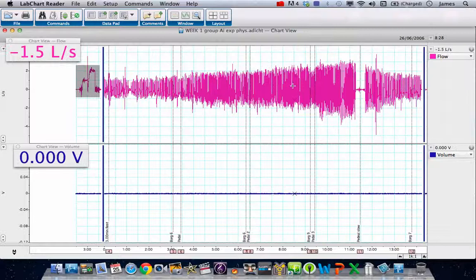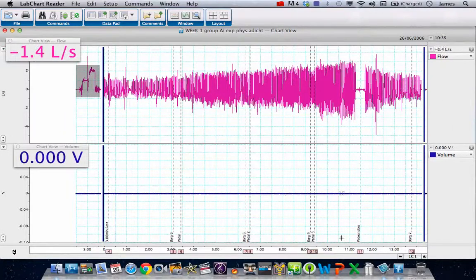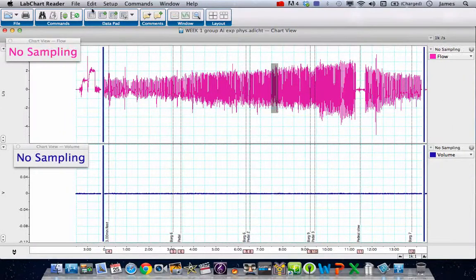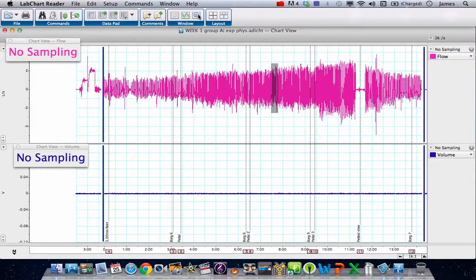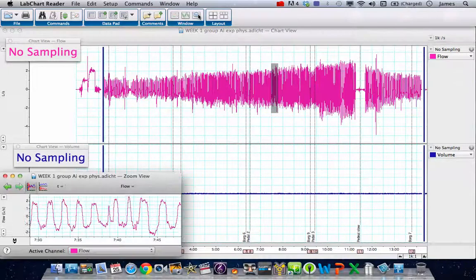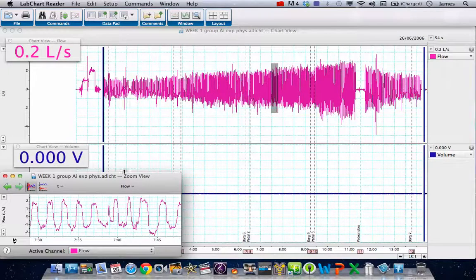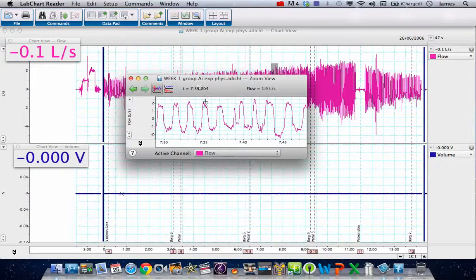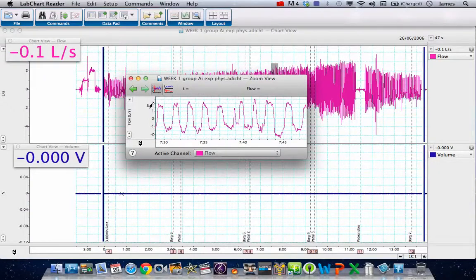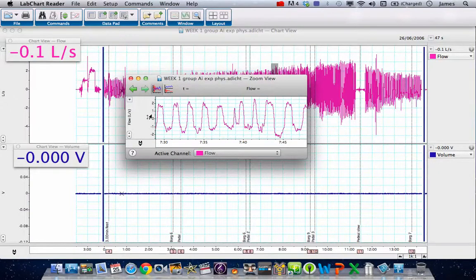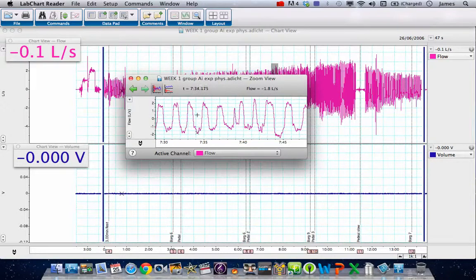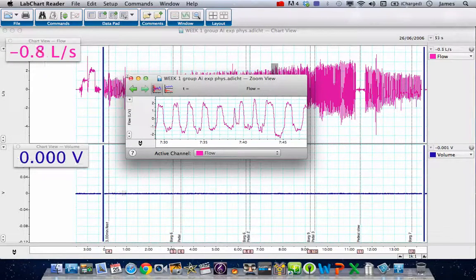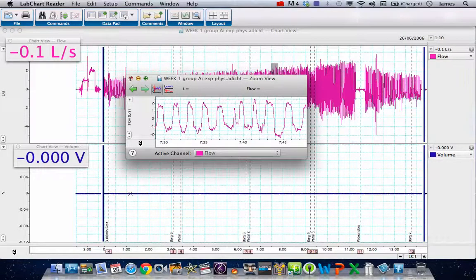Now our data here is calibrated. Let's zoom in on a very small section using the zoom window, and we can see that the flow is now calibrated. We've got in the scale bar here from zero to two and then from zero to minus two. Here is our flow rate as the person's breathing in and out. You can see it's clearly calibrated now, which is great.